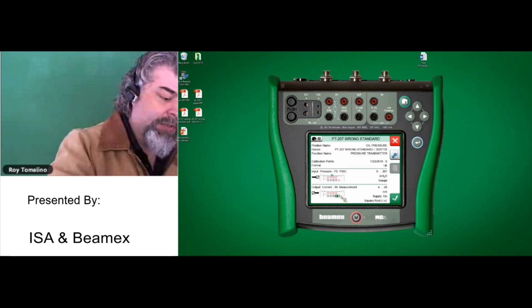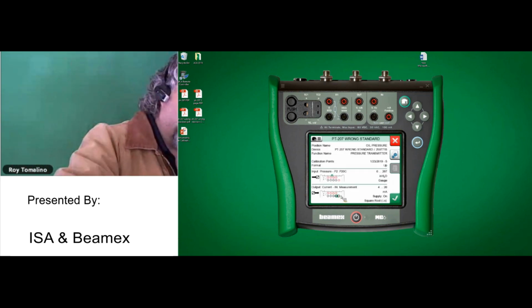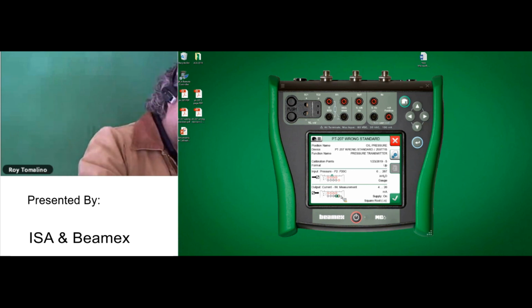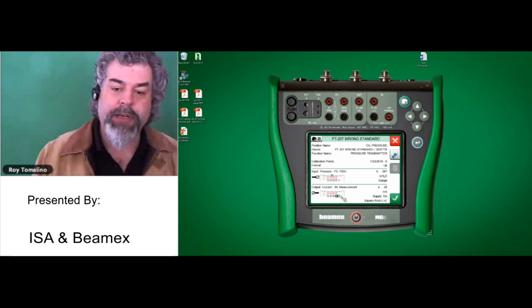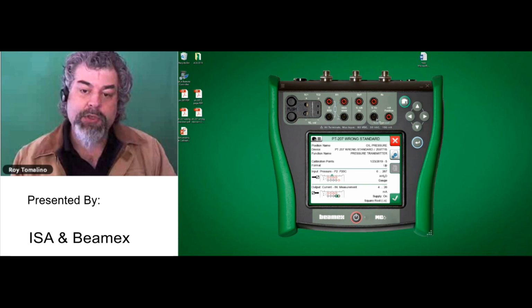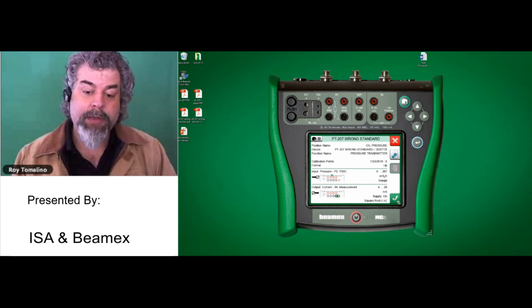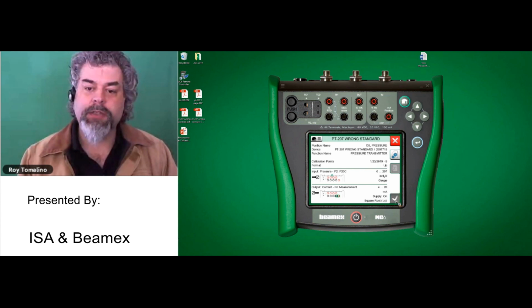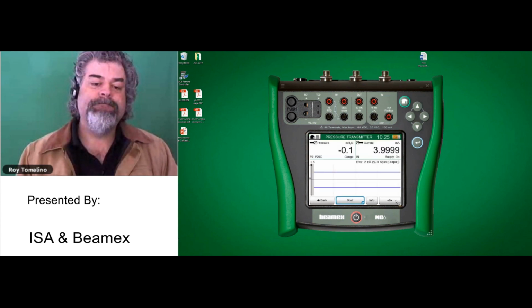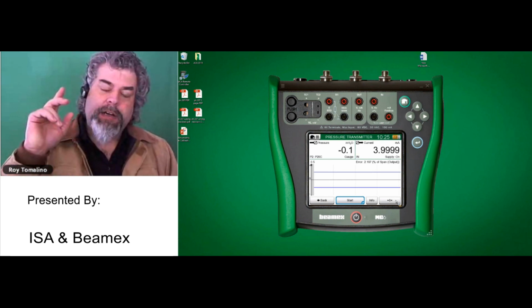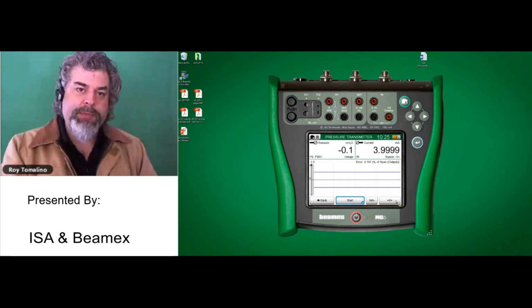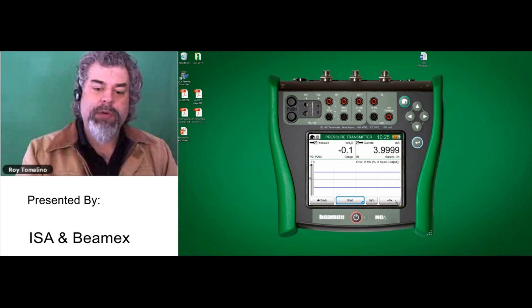And I need to hook up here across the bottom, so I'm powering up the transmitter at the same junction where I'm measuring current. And that's across these two right here where it says loop. So again, I'm measuring current and providing loop power. And this happens to be a square root transmitter. Let me hit the check mark. First off, on a differential pressure or a square root transmitter, we never want to calibrate it at 0.